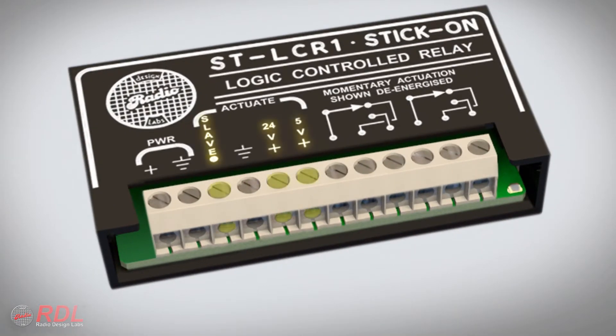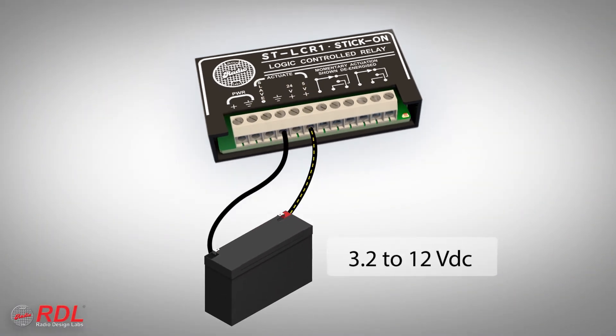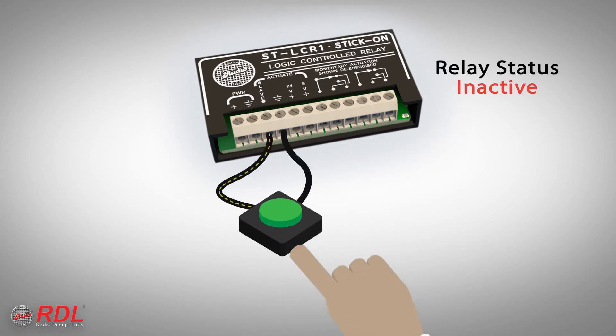Three different terminals may be used to activate the ST-LCR1. A positive DC voltage between 3 and 12 volts on the 5-volt terminal will activate the module. The 24-volt terminal activates on a positive DC voltage between 12 and 35 volts. The slave terminal also doubles as an input by activating the module when it is pulled to ground.